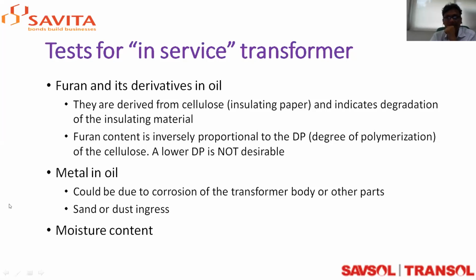Then the metal content of the oil, which can be seen by the metal content: there is corrosion of the copper or corrosion of other parts, and this metal comes into the oil. It might be insoluble, it might be in soluble form, or of very low solubility. So one has to do a periodic visual inspection of the oil and keep a strict eye on it. What is the color of the oil? The darker the color, the greater the indication that the oil is contaminated by soluble impurities like metallic salts and so on.